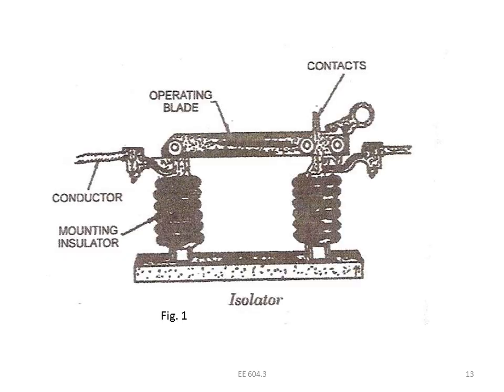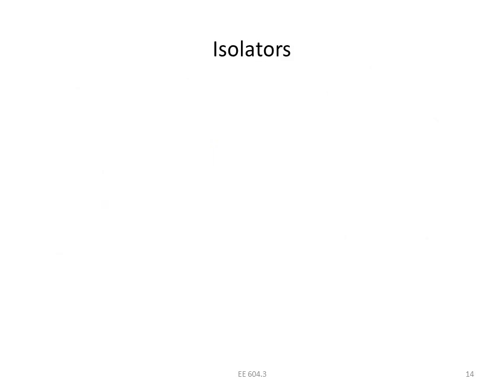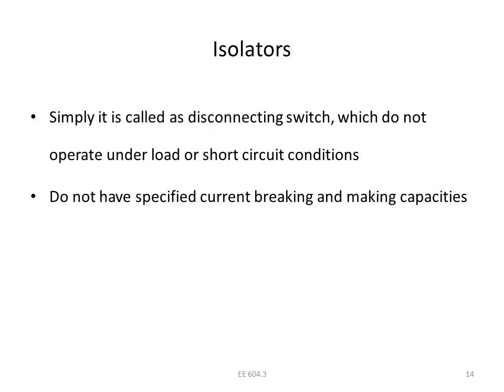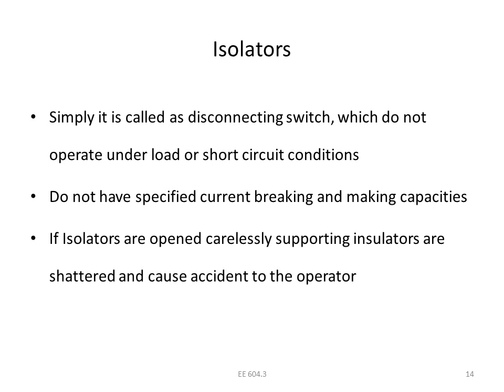This is the isolator. You can see the mounting, insulation, and the conductor input side and output side, and the blade, which will be turned. It is simply called a disconnecting switch, which does not operate under load condition. If it is turned under load, there will be a spark and arc formation, which causes huge damage. It is not specified for breaking and making currents.